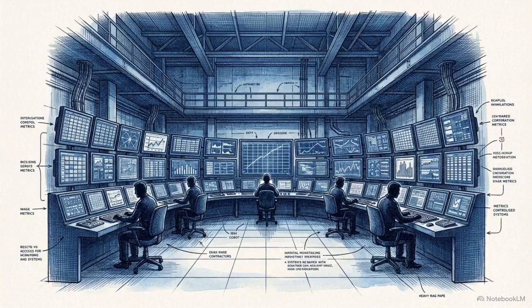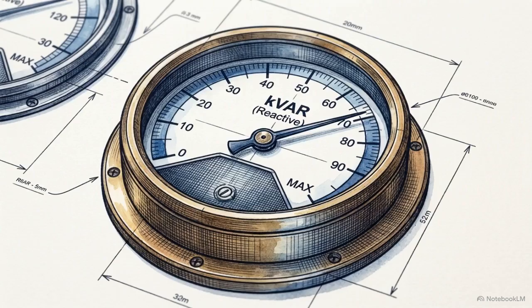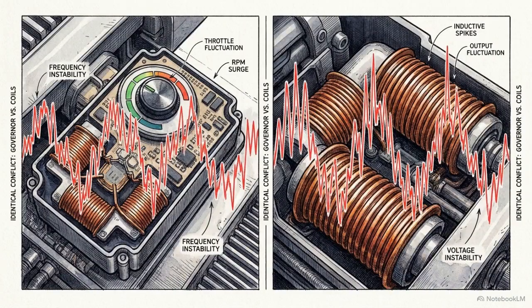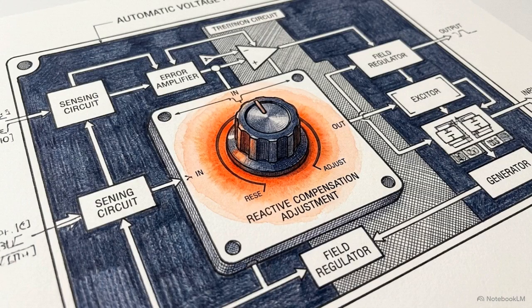This principle extends beyond the real active power governed by the turbine. The generator itself governs another critical component of grid load, reactive power, measured in kilovolt amps reactive. The exact same conflict we observed in frequency control has a direct parallel in stator voltage control. This block diagram outlines an automatic voltage regulator, or AVR. Its role is to maintain specific excitation and terminal voltage limits for the generator.